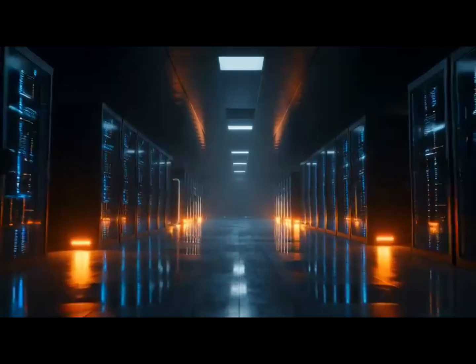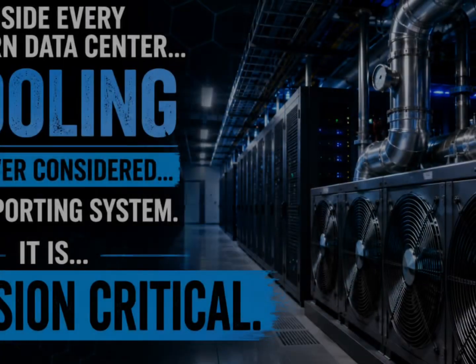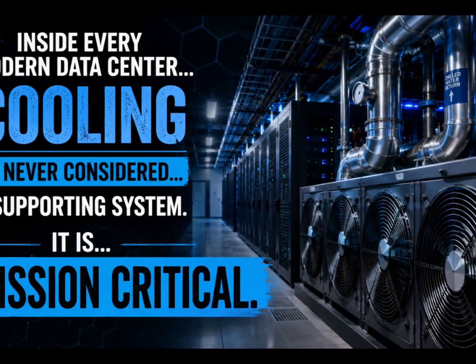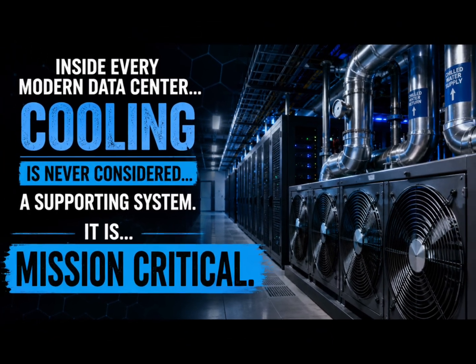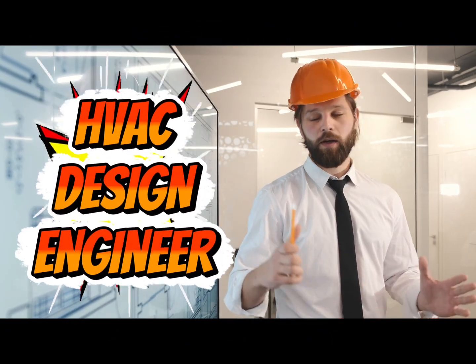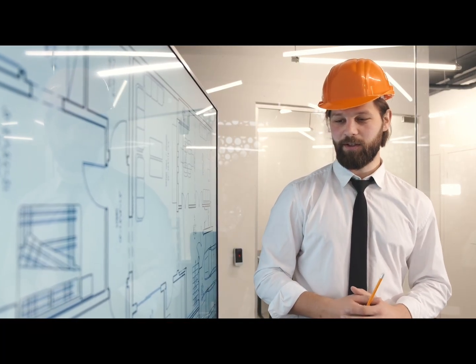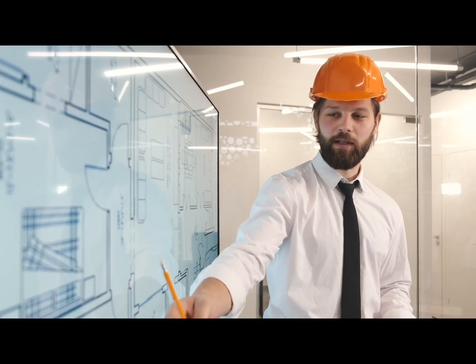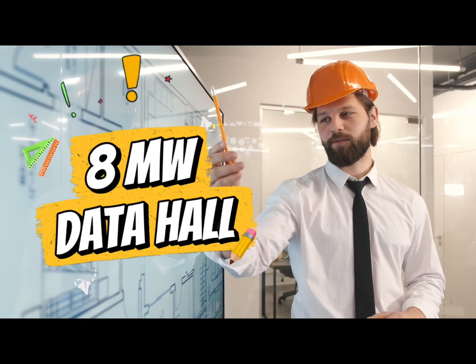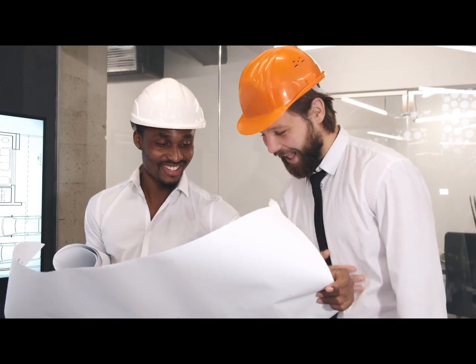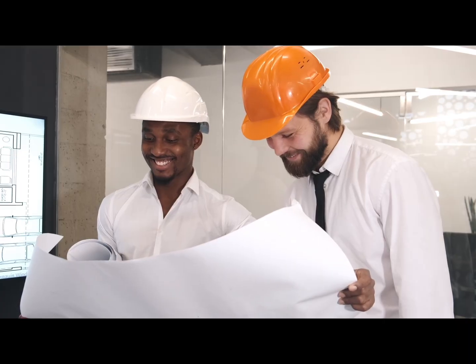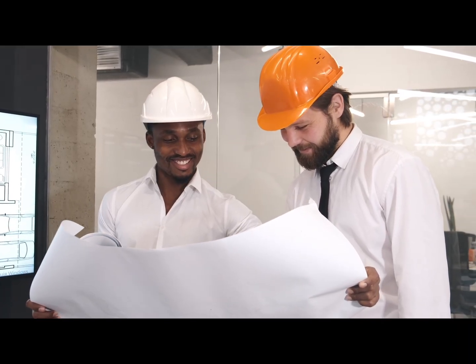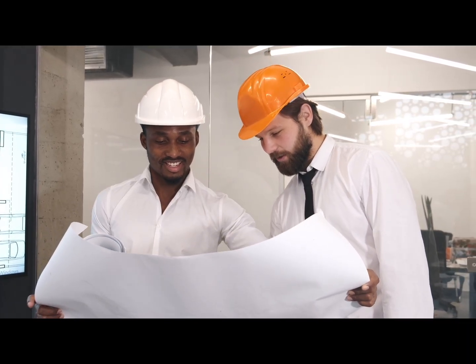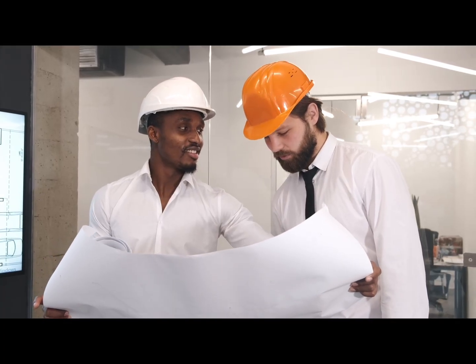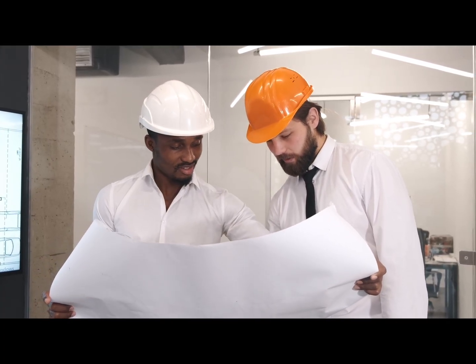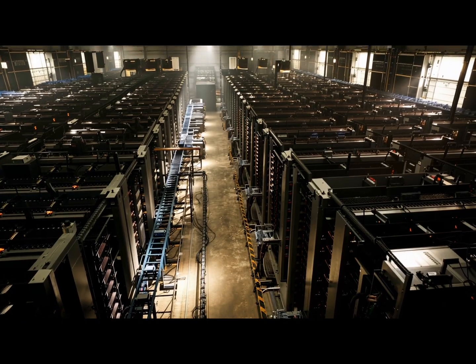That's why, inside every modern data center, cooling is never considered a supporting system. It is mission critical. Today, you are the HVAC design engineer. Your client has given you a challenge. Design the cooling system for an 8-megawatt data hall. Choose equipment that is too small, and the servers overheat. Choose equipment that is too large, and millions of dollars are wasted. So how do engineers determine the exact cooling capacity a data center requires?